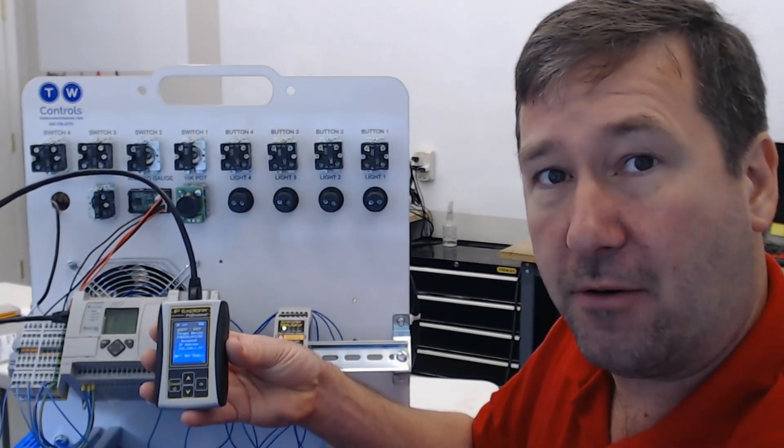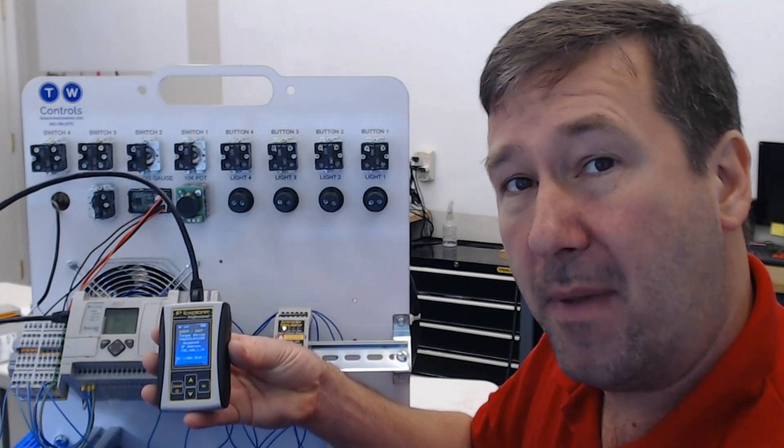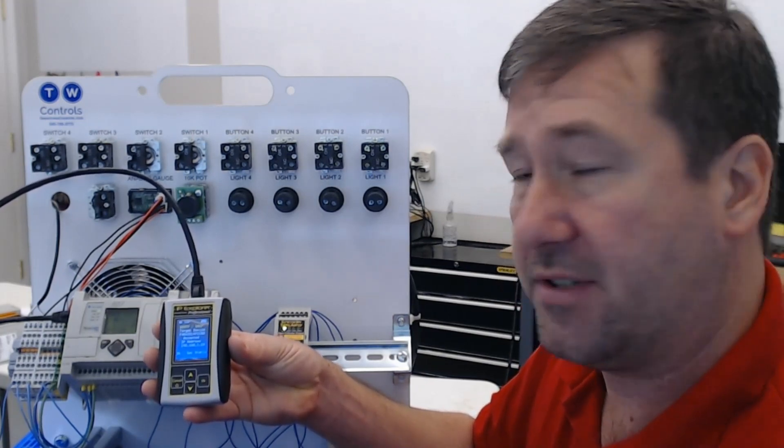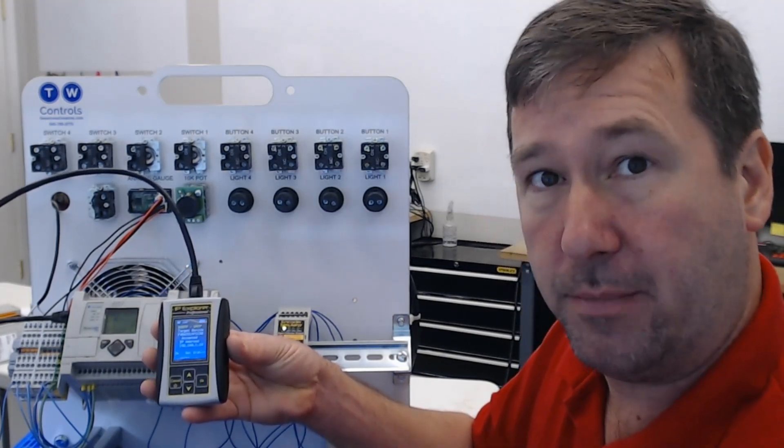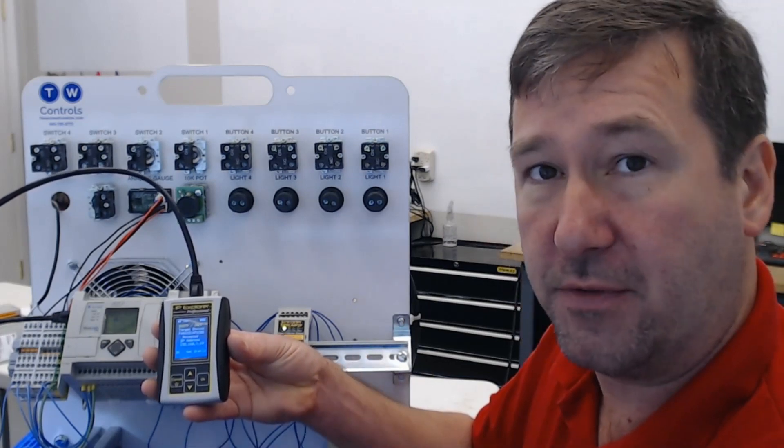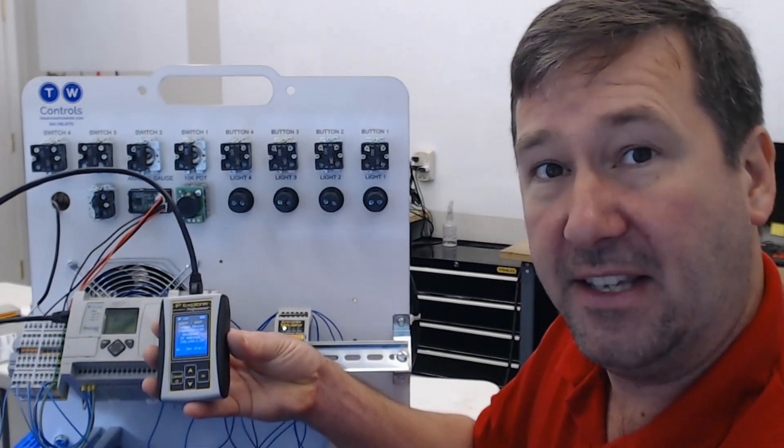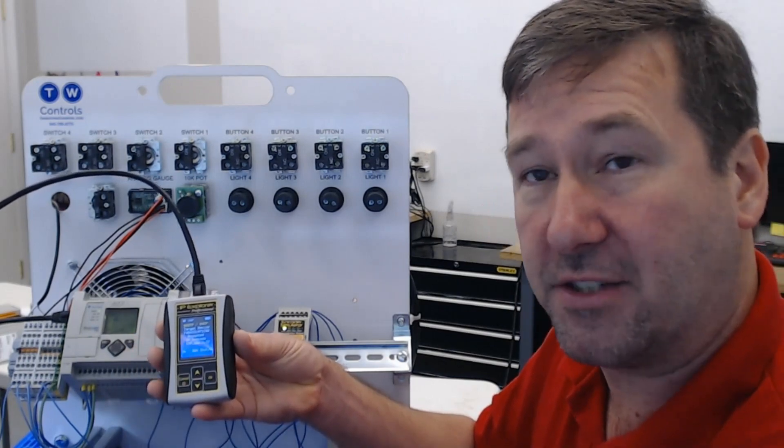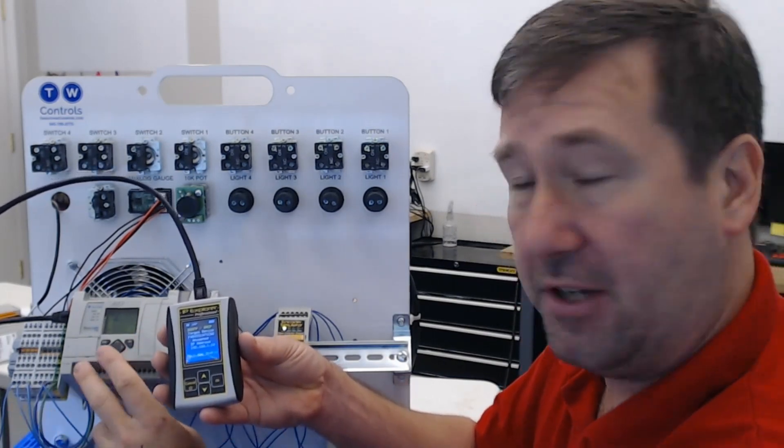If you've had yours powered up for more than a minute or so, it may quit making requests. Most devices only make bootp or DHCP requests for the first few minutes after power up, and then they stop. So if it's stuck on that waiting screen, just cycle the power to your device.